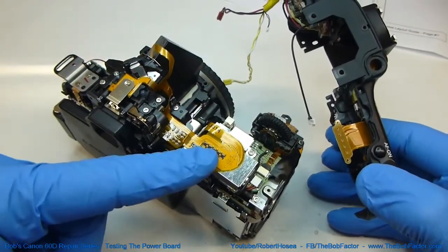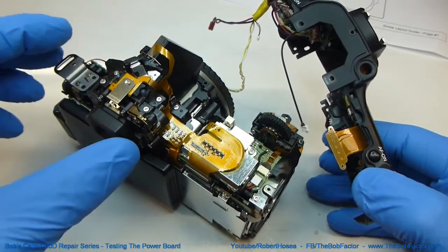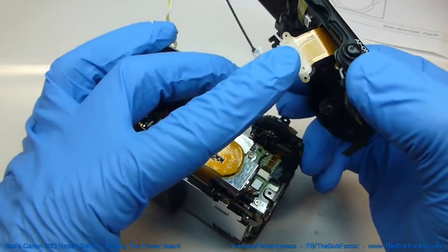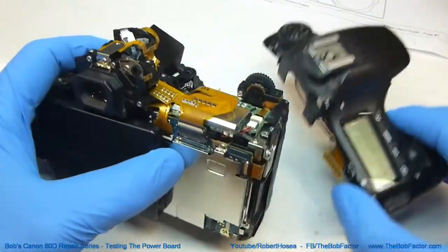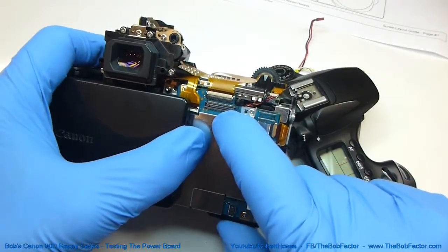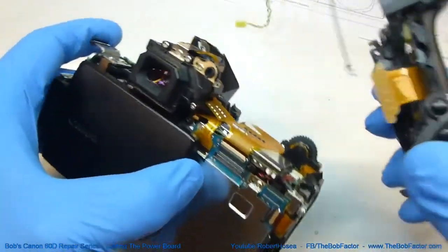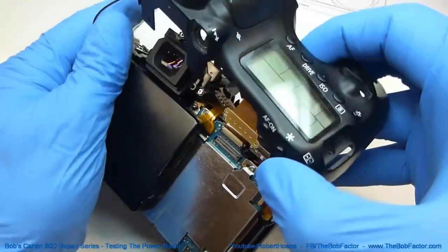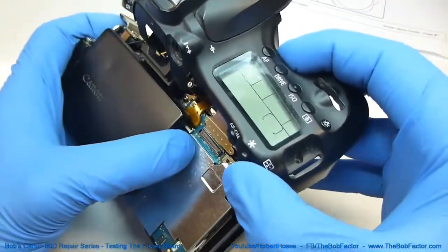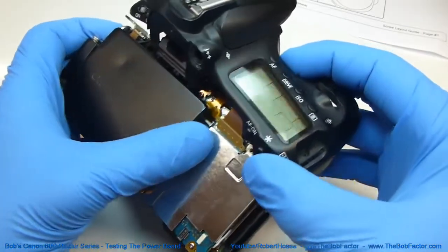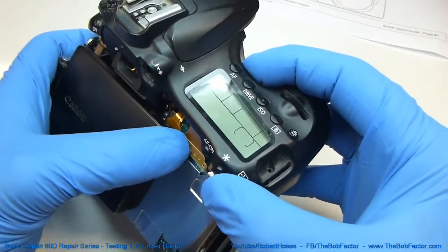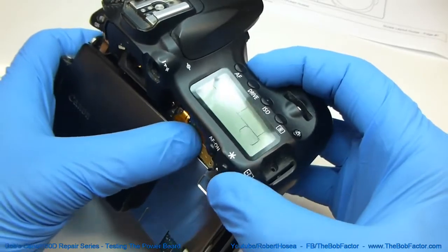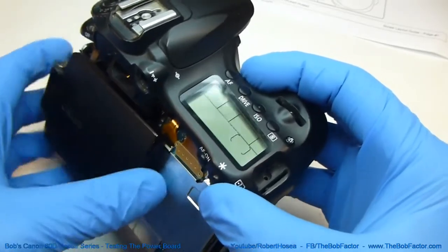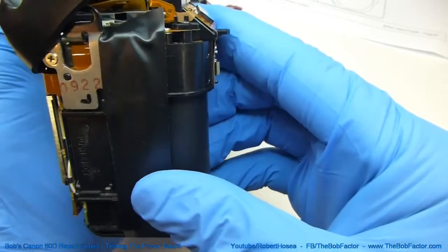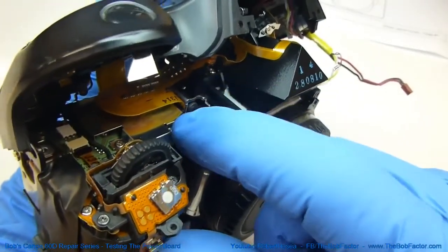For the next readings, we're going to need to turn the camera on. To do that, we need to hook this flat ribbon cable on the top piece back to the socket on the main board. I hold the top piece up at an angle and get it down as far as I can, to where that cable reaches the socket. Then push it on, and leave the top piece at an angle like that, which gives us access over here to the power board.